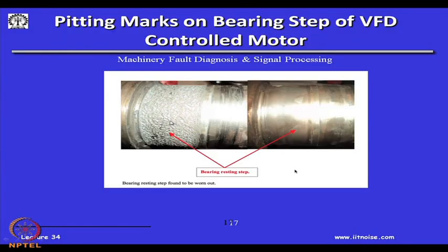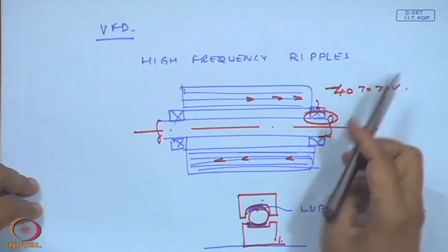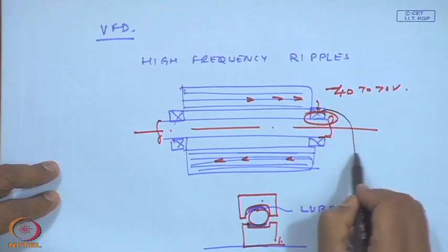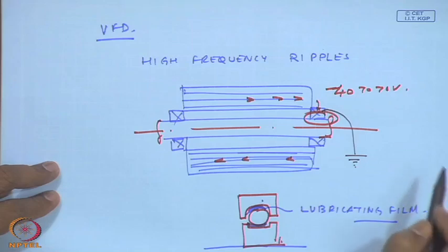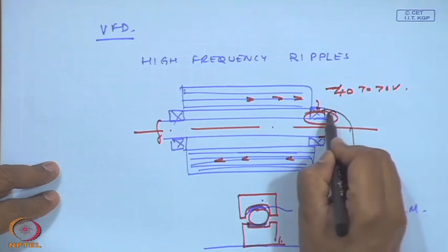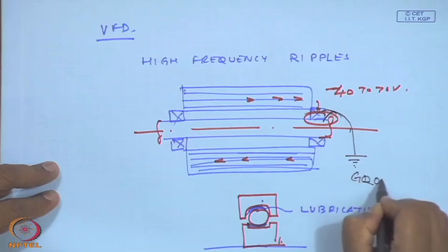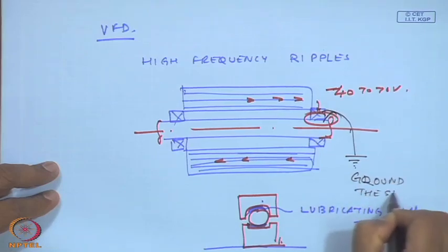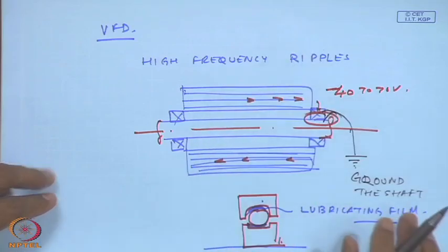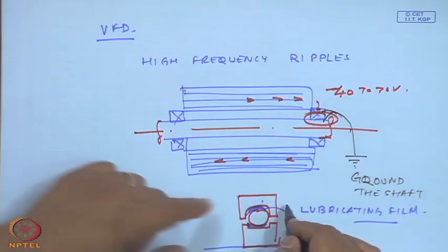So, if this goes undetected, particularly in variable frequency drives, because of these high frequency ripples, there will be sparking on the surface. The shafts become worn out like this, and shafts become weak. So how do you take care of it? You have to produce an alternate path for this current by grounding the shaft. Shaft to the grounding brush, so that the current flows through that route, and there is no discharge taking place.